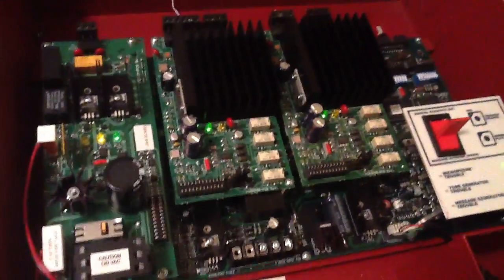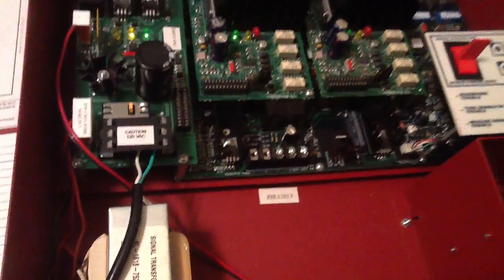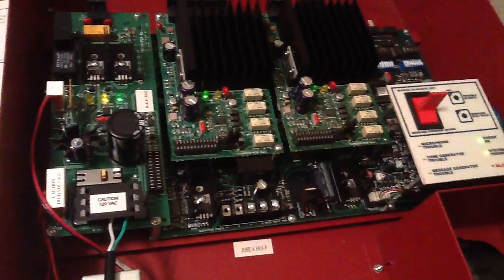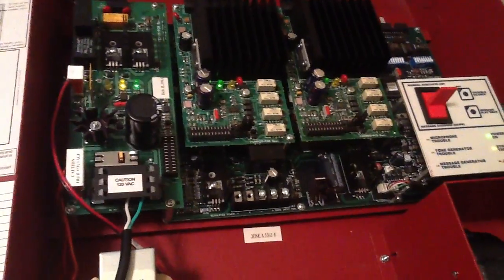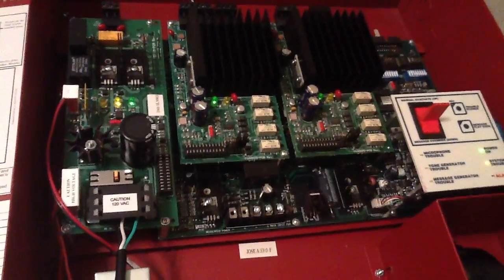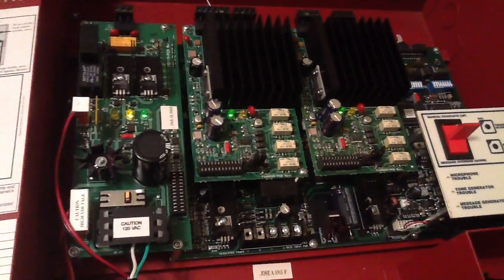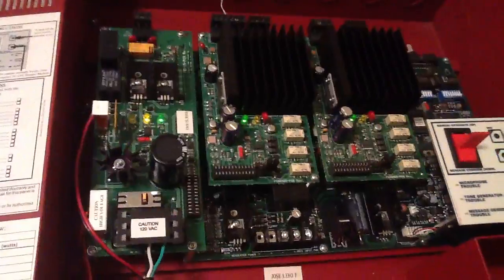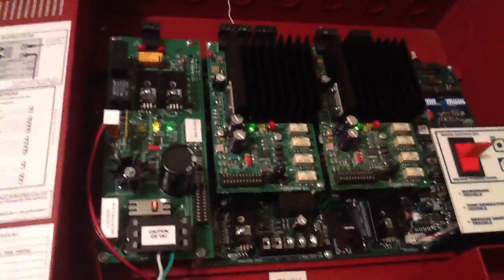The biggest thing was that the amplification was built into the system, and it's also on a battery backup. So it's a much more complete life safety system than the setup I had before, because if there was a power failure in the last setup, the ELK card would not work — you would just have the strobes and no message. Anyway, I think it'll work well in the system.